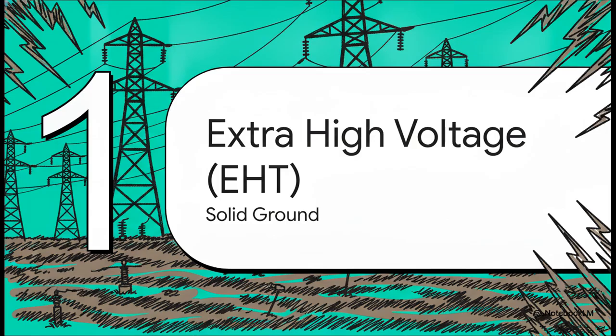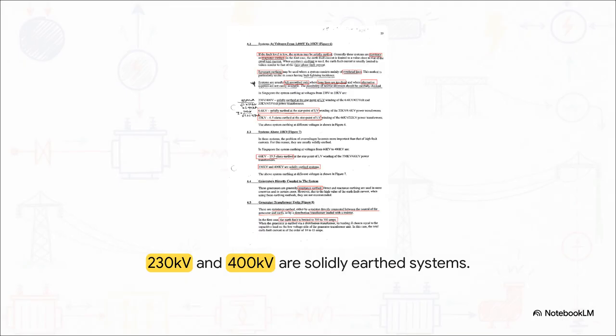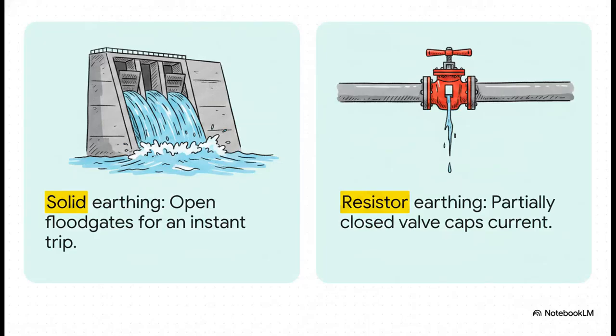First up, extra high voltage, or EHT, solid ground. The engineering documentation is incredibly explicit on this. Both the 400 kilovolt and the 230 kilovolt sides of EHT transformers are solidly grounded, period. There is absolutely zero resistance deliberately inserted between the neutral point and the earth. To really grasp why we do this, just think of a massive dam holding back water. Solid earthing? It's like opening the floodgates completely for totally unrestricted flow. On the flip side, resistor earthing acts more like a partially closed current-limiting valve. But up here at the very top of the grid, we want those floodgates wide open.